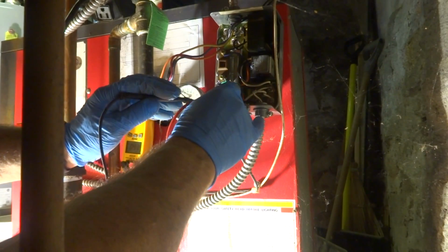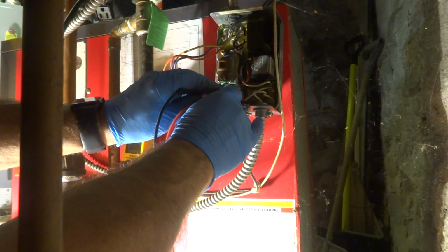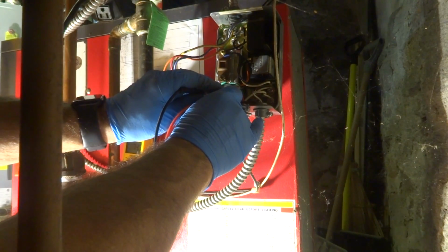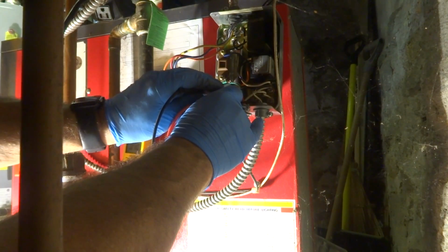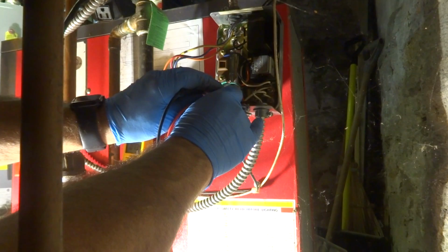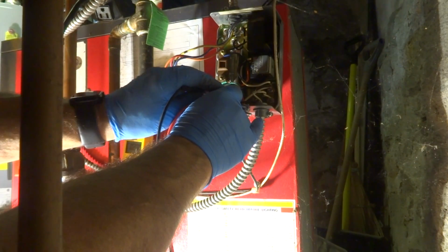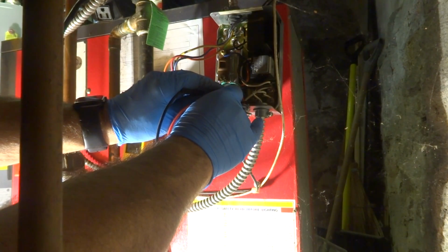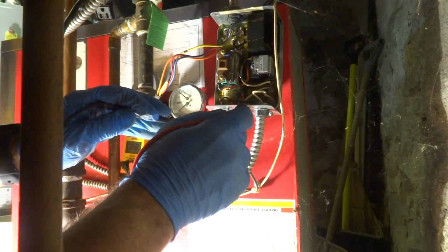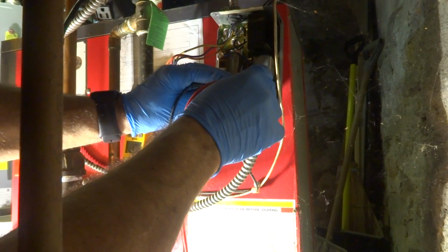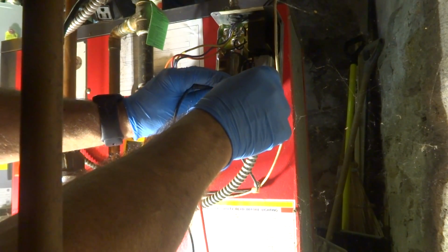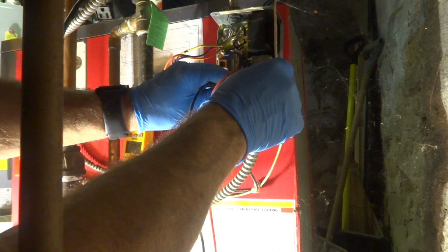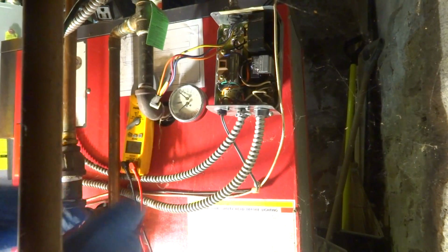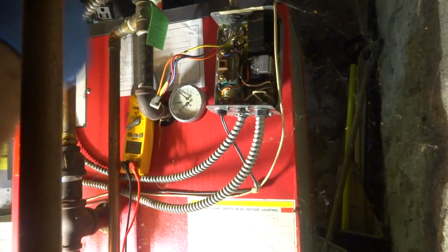And if I go common and I go neutral here, I'll see if any of these are live. I got no voltage, nothing, and I got 110. I got 110 coming in, and I got 110 for the circulator, but nothing going through this control part.